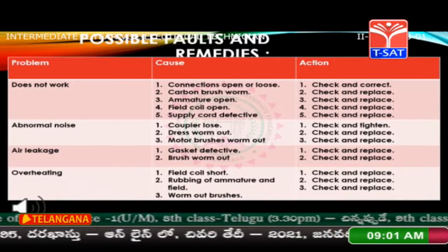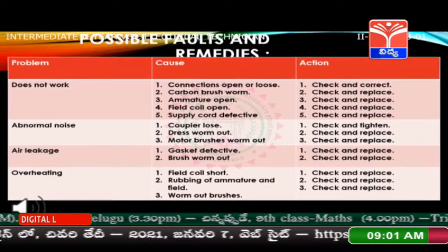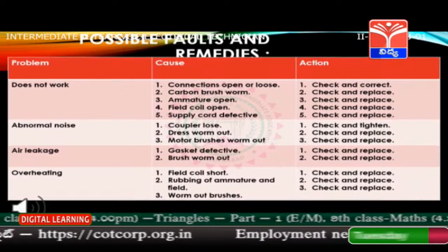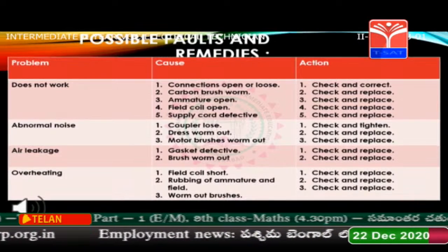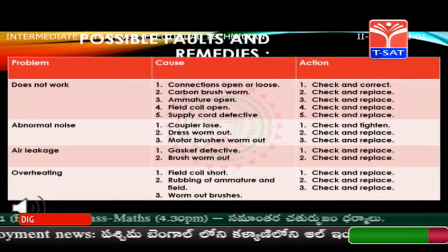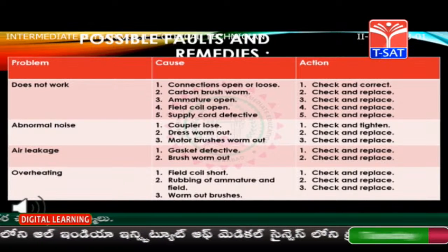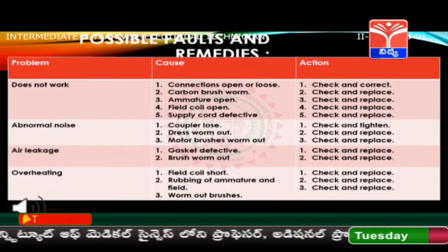Air leakage. Problem is the air leakage. Cause: gasket defective. Check and replace the gasket. Problem 2: brush worn out. Check and replace.